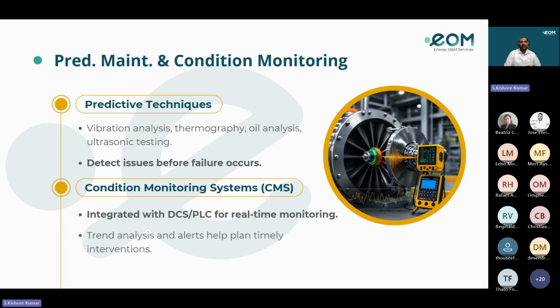Sometimes wrong signals or wrong data will lead to turbine trips. So the vibration analysis has to take place, and the vibration sensors have to be inspected and calibrated at intervals. Thermography analysis, oil analysis, and ultrasound testing also detect issues before the failure occurs.